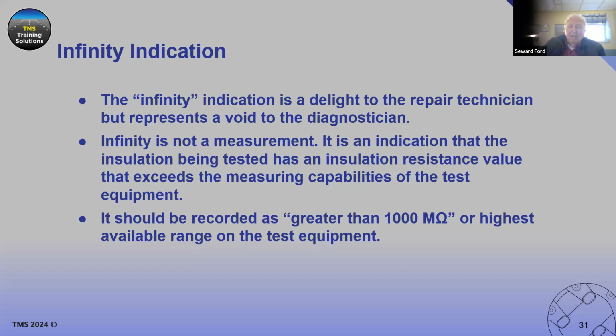Well, then we go down: infinity is not a measurement. It is an indication that the insulation being tested has an insulation resistance value that exceeds the measuring capabilities of the test equipment. You say it's an infinity reading. It's got an infinite Megger capability, but that's only true for the instrument that you're using. If you were using a different tester, maybe a different voltage, that wouldn't be true. So you've got to at least state on that report, it should be recorded as greater than 1,000 megohms or highest available range on the test equipment.